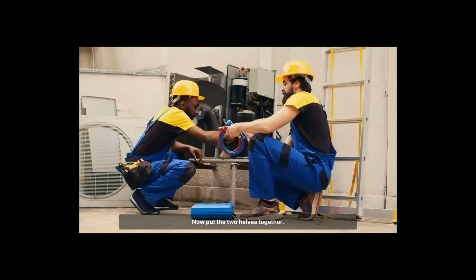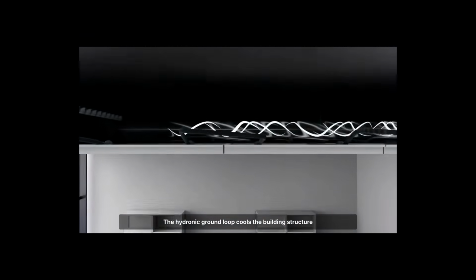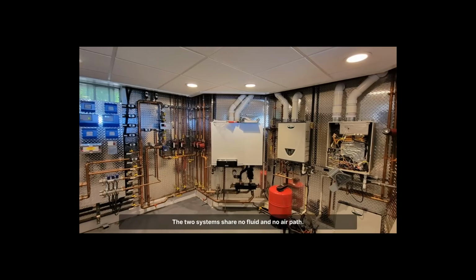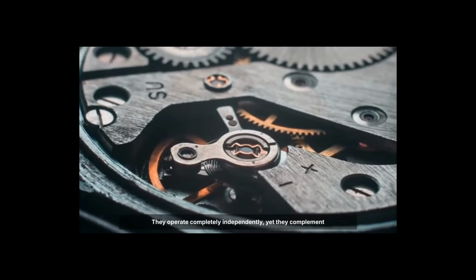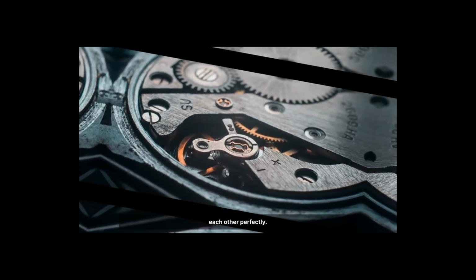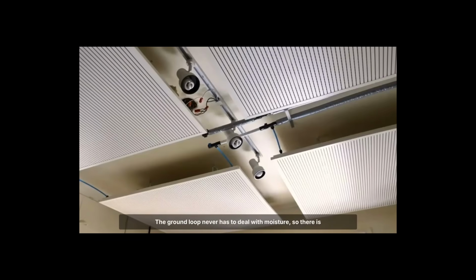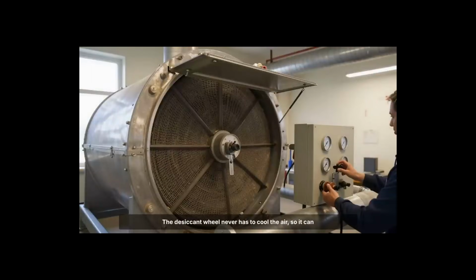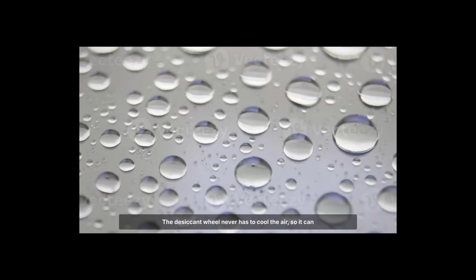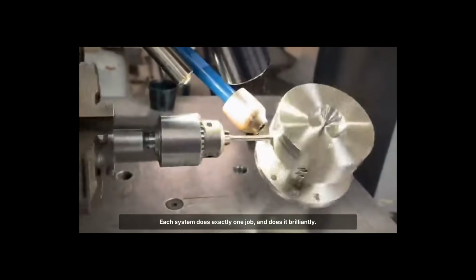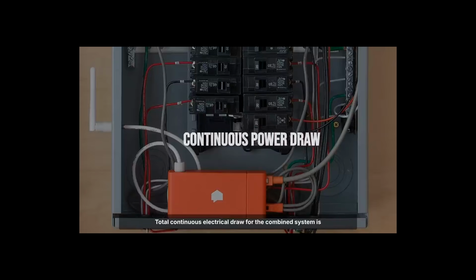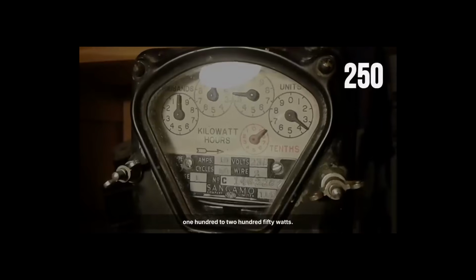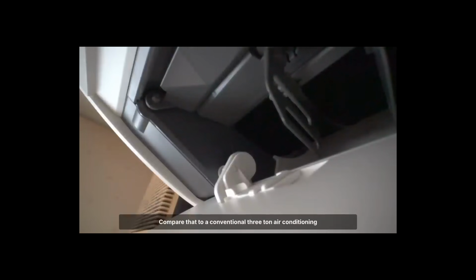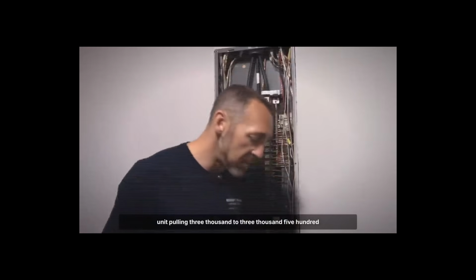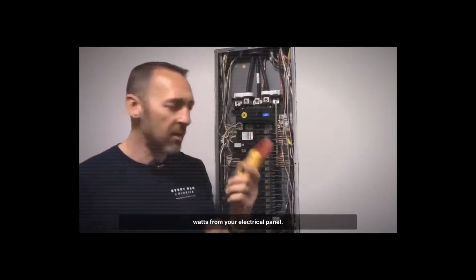Now, put the two halves together. The desiccant wheel strips moisture from incoming ventilation air. The hydronic ground loop cools the building structure through radiant surfaces. The two systems share no fluid and no air path. They operate completely independently, yet they complement each other perfectly. The ground loop never has to deal with moisture, so there's no condensation risk on cooling surfaces. The desiccant wheel never has to cool the air, so it can focus entirely on drying. Each system does exactly one job and does it brilliantly. Total continuous electrical draw for the combined system is 100 to 250 watts. Compare that to a conventional 3-ton air conditioning unit pulling 3,000 to 3,500 watts from your electrical panel.